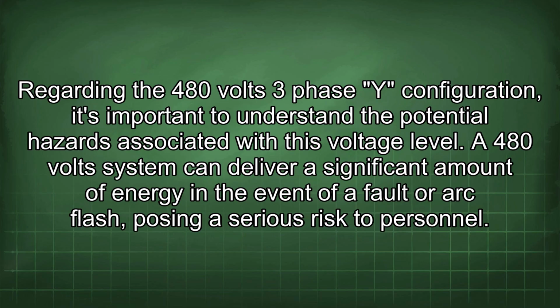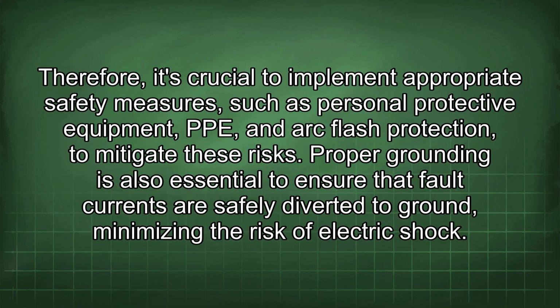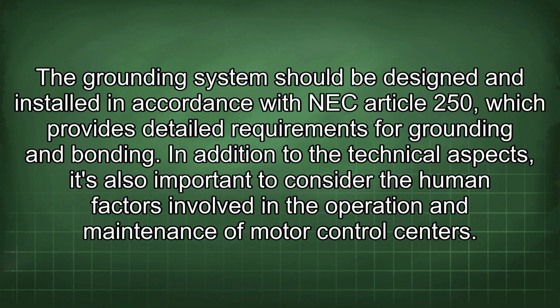Regarding the 480 volt 3-phase Y configuration, it's important to understand the potential hazards associated with this voltage level. A 480 volt system can deliver a significant amount of energy in the event of a fault or arc flash, posing a serious risk to personnel. Therefore, it's crucial to implement appropriate safety measures such as personal protective equipment (PPE) and arc flash protection to mitigate these risks. Proper grounding is also essential to ensure that fault currents are safely diverted to ground, minimizing the risk of electric shock. The grounding system should be designed and installed in accordance with NEC Article 250, which provides detailed requirements for grounding and bonding.